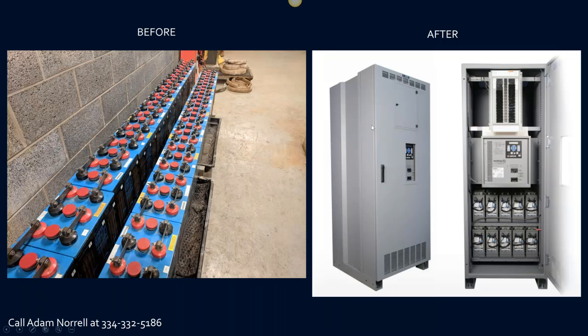And over to the right is a solution we've used lots of times over the past few years. It's a battery, charger, and DC panel all integrated into one enclosure. So you've taken this 150 linear inches of batteries, and you have consolidated all that into, say, a 36 or 40-inch wide enclosure that has the charger, batteries, and the DC panel pre-integrated, pre-tested into an enclosure. Very cost-saving, time-saving piece of equipment.